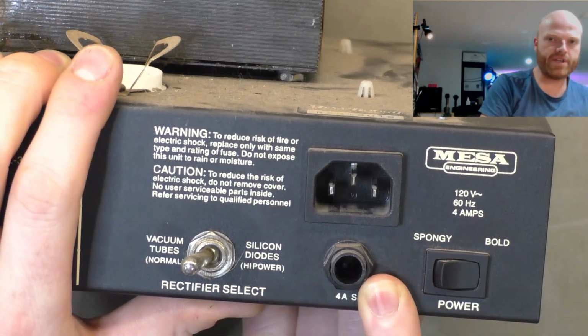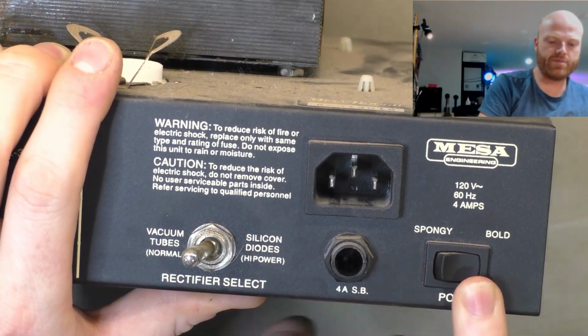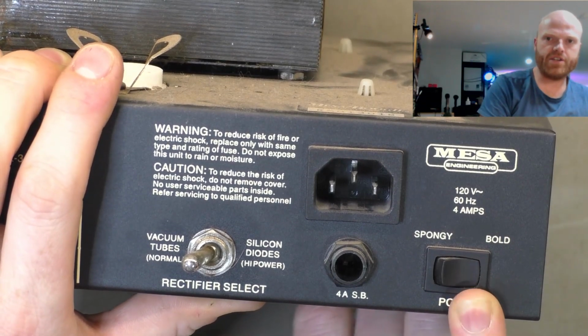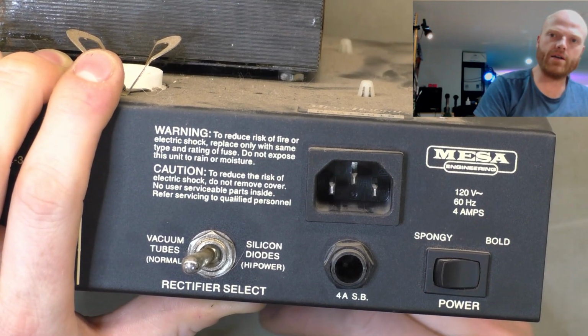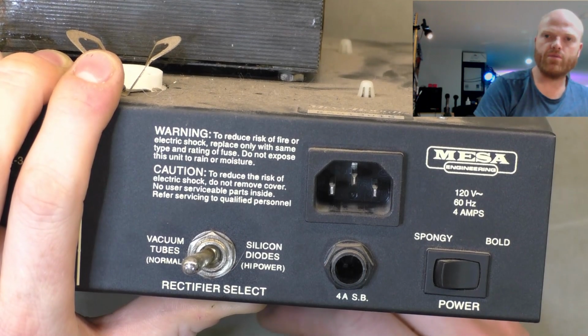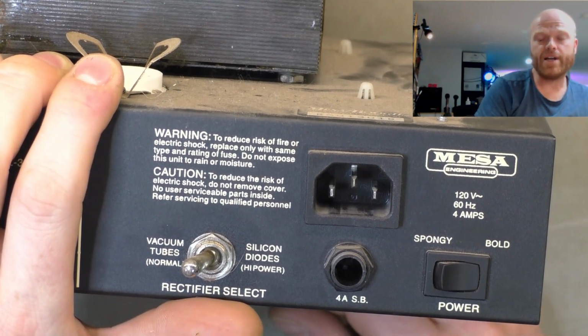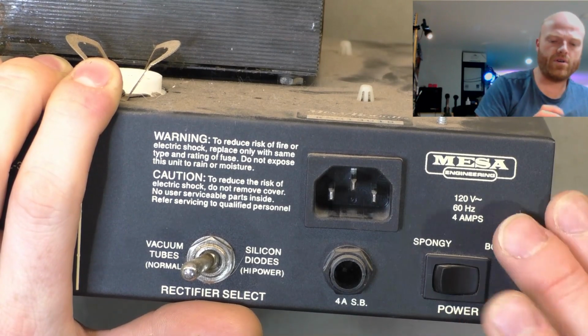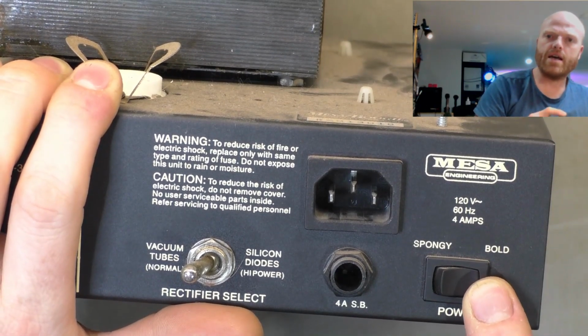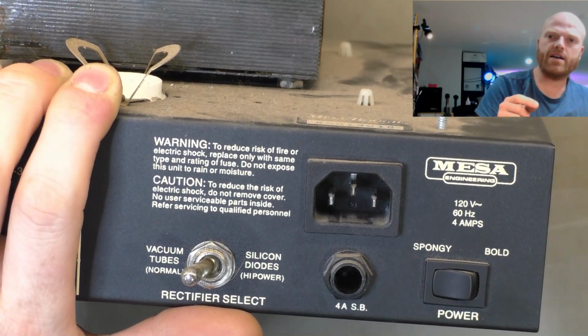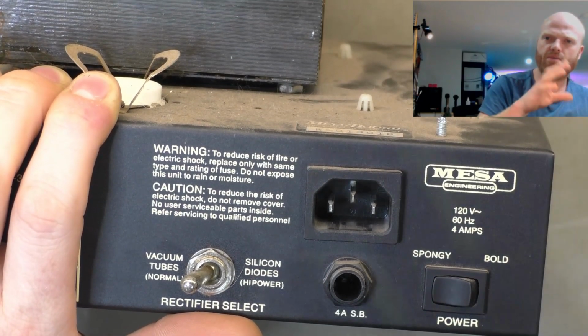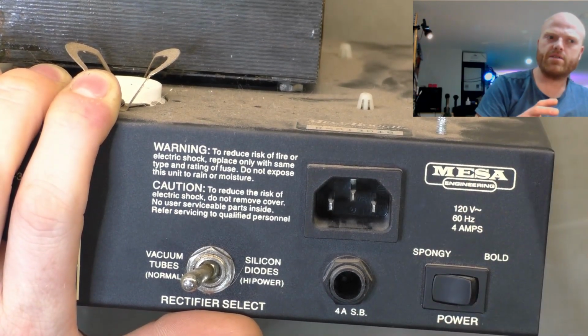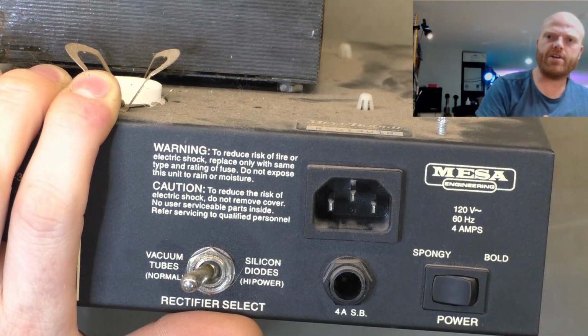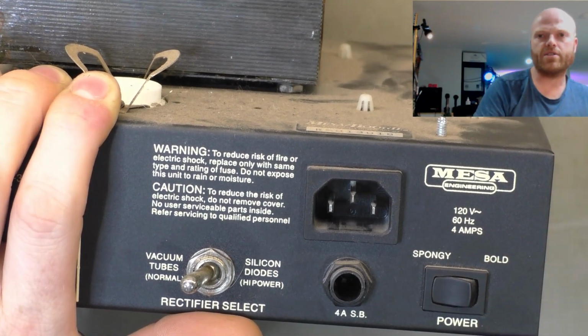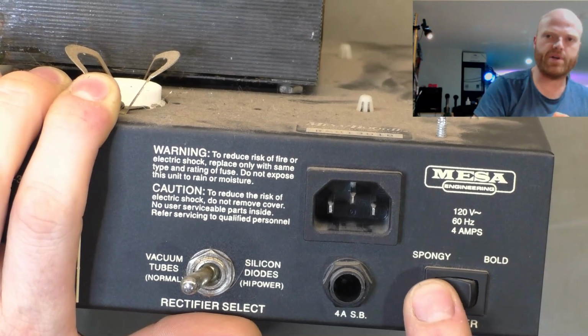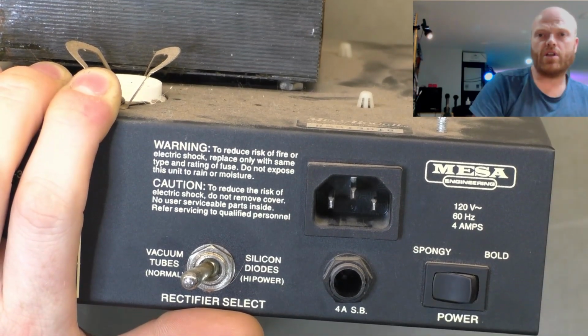Obviously you've got your fuse there, which I've taken out to check, and you've got a spongy/bold switch. Now that changes to a higher voltage tap on the primary actually. So on bold you've got your full power, and then when you go to spongy, I believe it adds more windings, so the primary has got a greater turn ratio to the same amount of turns on the secondary. So the effect is when you're on spongy, all your voltages are lower.